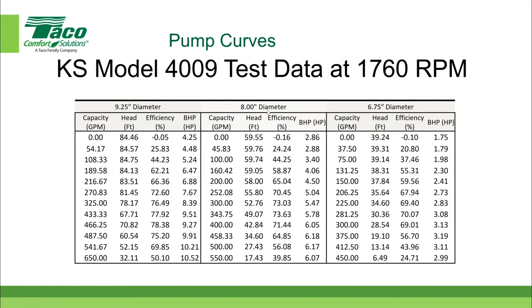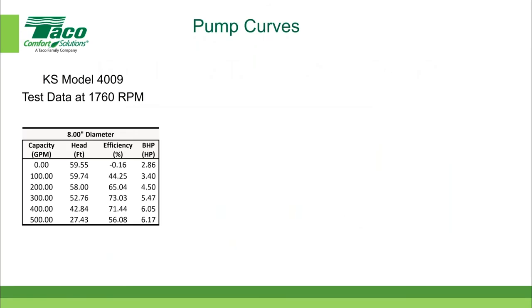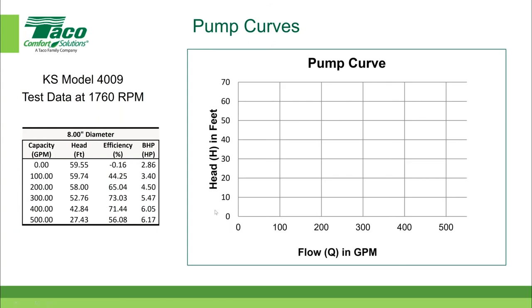Let's look at just the 8-inch diameter impeller data. We take the flow on the horizontal axis in gallons per minute and the differential pressure in feet — in the pump world we call differential pressure across the pump the 'head' of the pump. Flow is in gallons per minute and differential pressure is in feet of water column. We take the data collected in the laboratory and plot it. The first data point is zero GPM and roughly 60 feet of head.